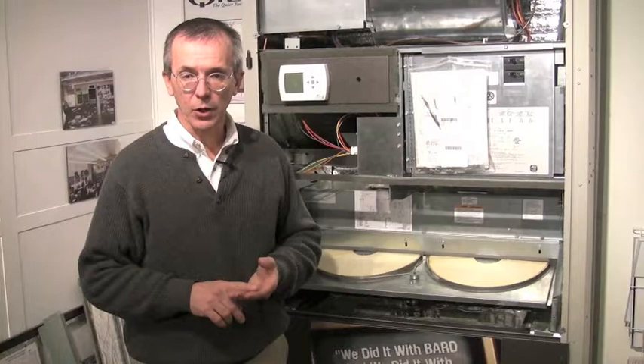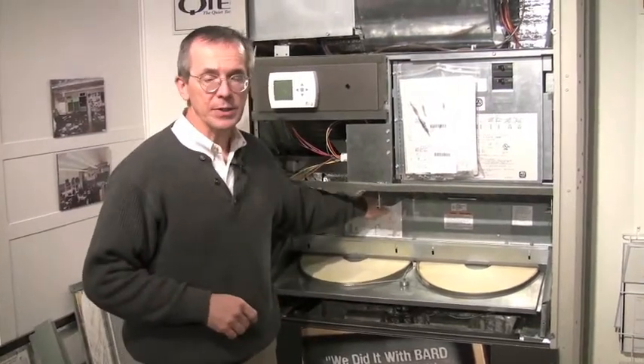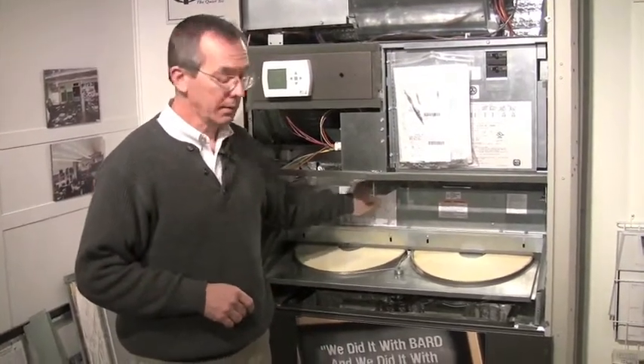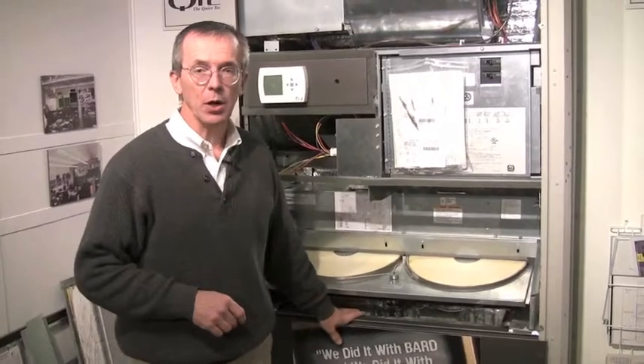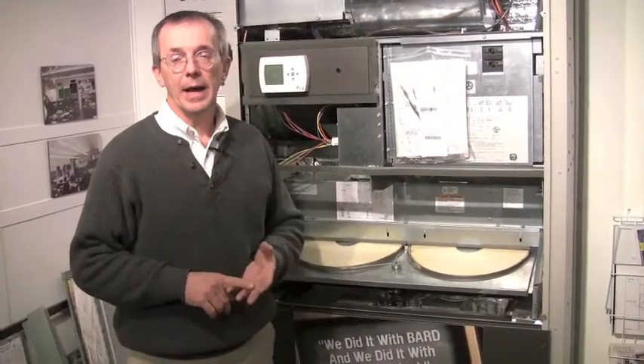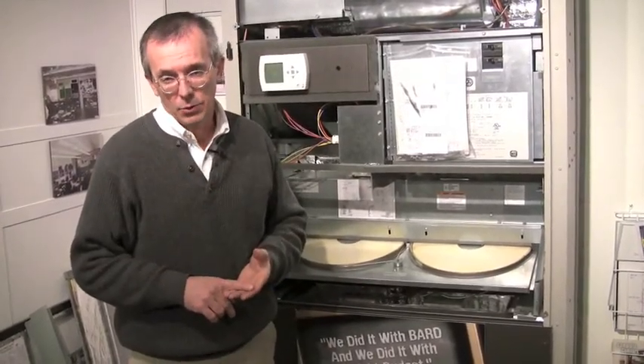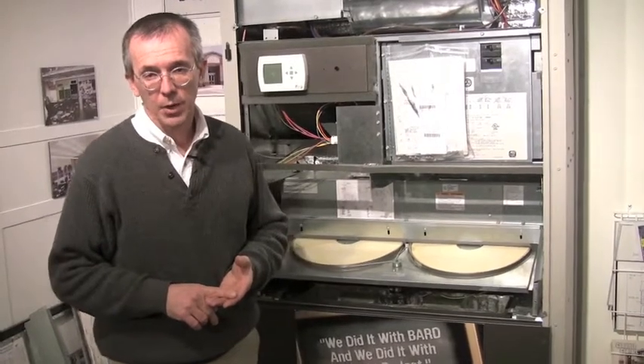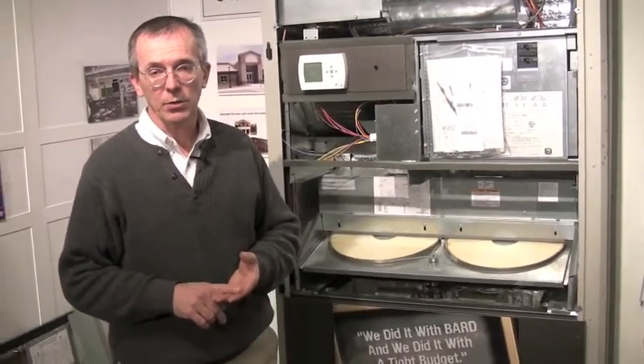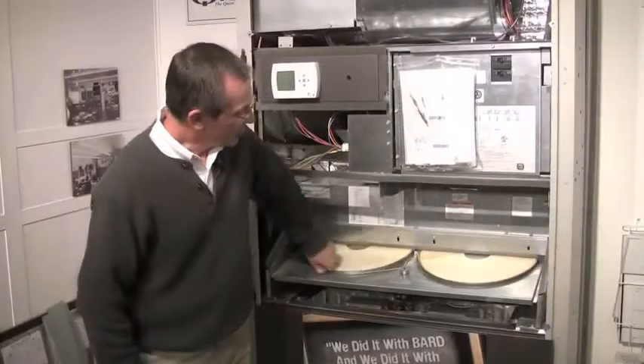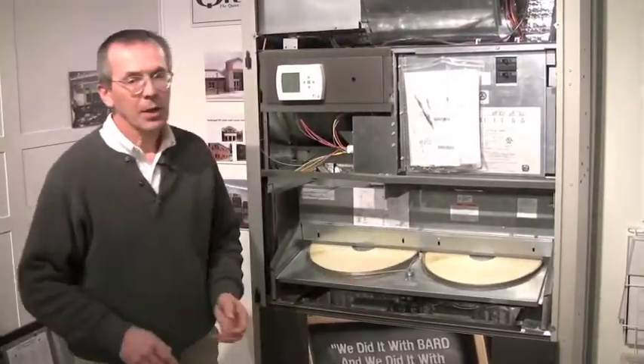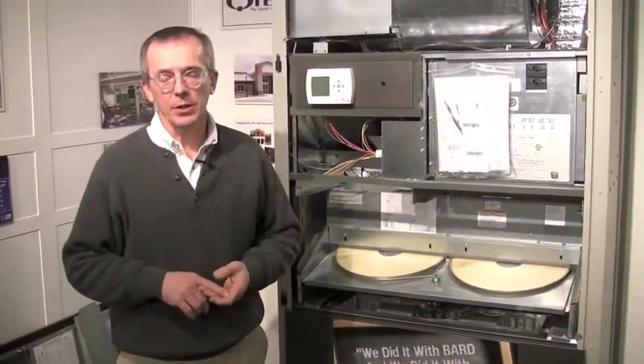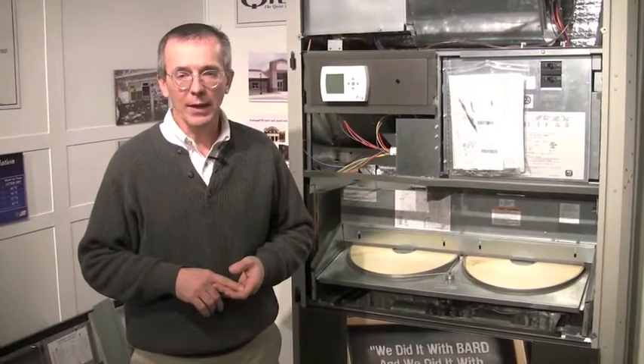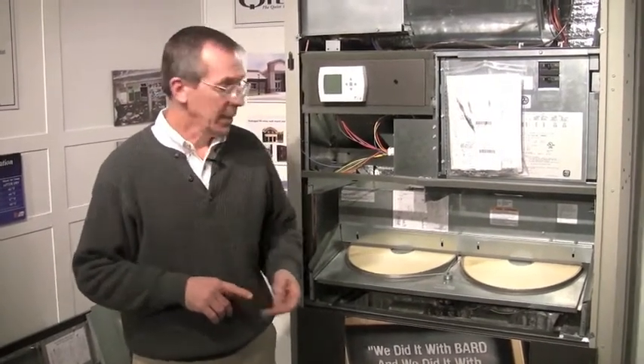From the factory, the unit comes with 375 intake and 300 exhaust. That happens to be to pressurize the room. They can be changed in the field to any setting. The wheels turn just about this fast. Again, this unit is a 3-ton unit, so we're at a nominal 1100, 1200 CFM.